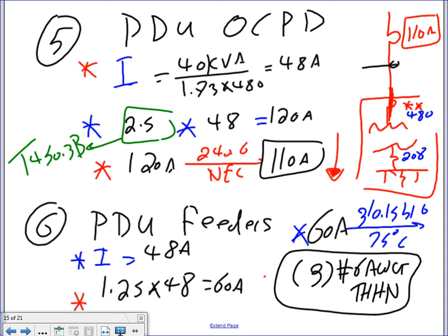We got number 6, that's about it. So these are all the sizes that we did. So that's my PDU, on the secondary side, that's what we size. When you ask the PDU manufacturers, they typically have a panel attached to the PDU. For example, with the 40 here, they will have a panel. What's the full load current on the secondary of the PDU? Take 40 divided by 1.73 divided by 208. So on the secondary side, this panel most likely will be a 125 amp panel with all these circuit breakers, 20 amp, 20 amp. But these will be sized by the manufacturer.